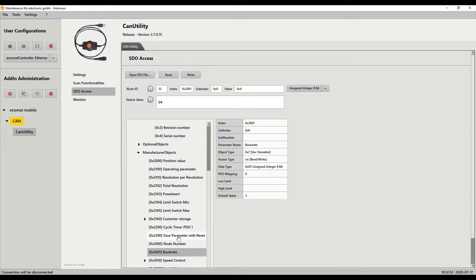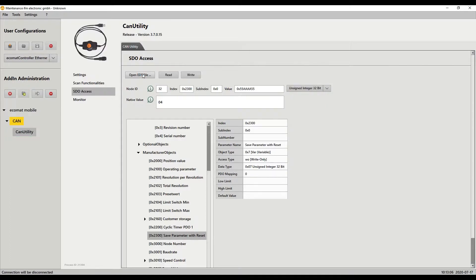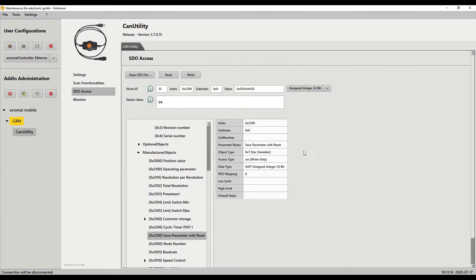The last part is I do this save parameter reset. Here I have to enter the 0x55AAAA55 and write, and at this point it's all done. Now all that's required is to do a power cycle of the device and you'll be good to go. So we change the value to 250 with a node ID of 16. At this point make sure again that you have power cycled the device and you should be good to go.